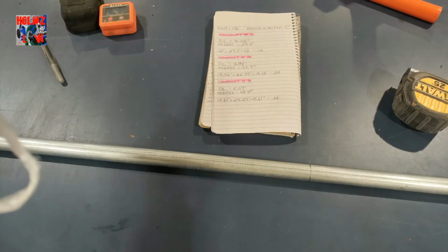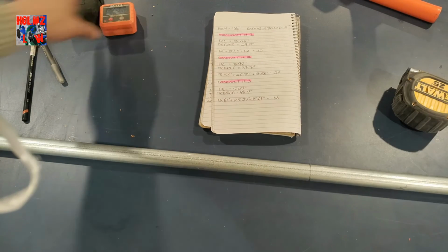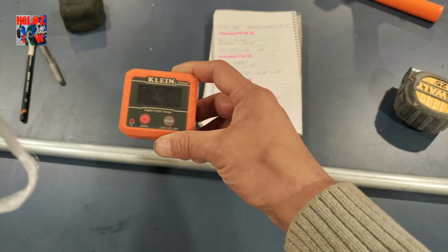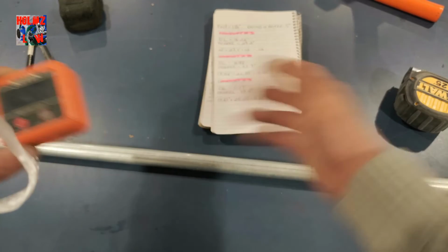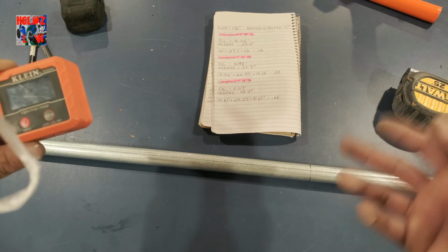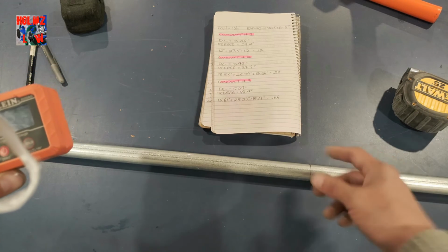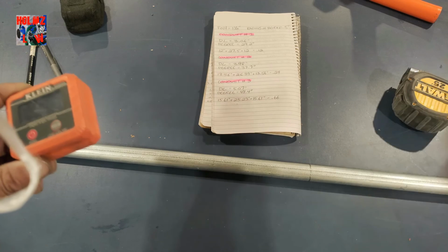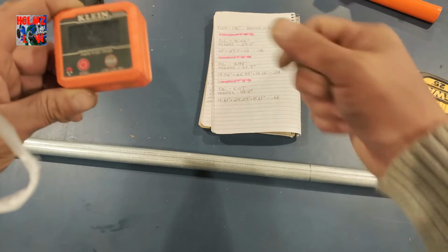Now, one thing I want to let you know is when you're bending with a hand bender, you're going to use a digital level, and that's how you can get these non-standard degrees. If you're lucky enough to be on an electric bender, that's even better because you can just punch in the degree that you want and bend it. Or if you're on a table bender, same thing. If you're using a hand bender, it's a little different because you have to bend and see where you're at, but it works.